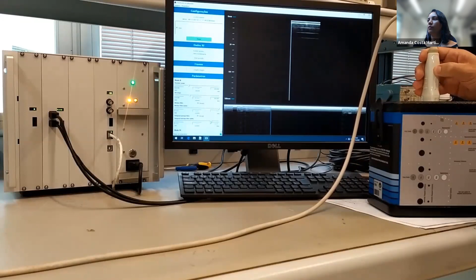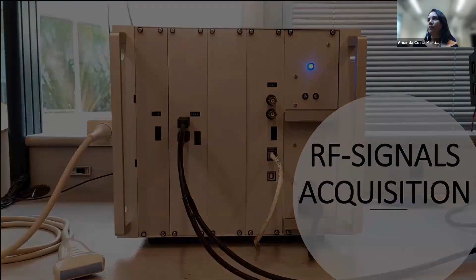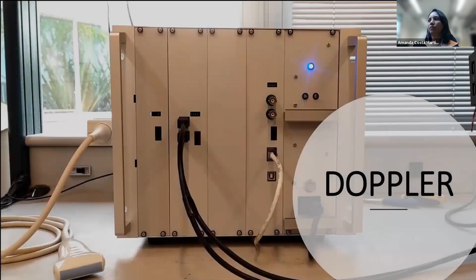Through a slider line, it is possible to scan any B-mode scanline and show it over time as M mode, which has the same dynamic range and independent gain settings as B mode. It is possible to visualize a line in the time domain in a fixed region of the graphical interface. It is important to note that the visualized signal is in real time and has no processing or filter. It is the signal digitalized by the analog to digital converter, also called raw data or RF signal. It will be necessary to set the parameter line echo active equals to true in the configuration file.